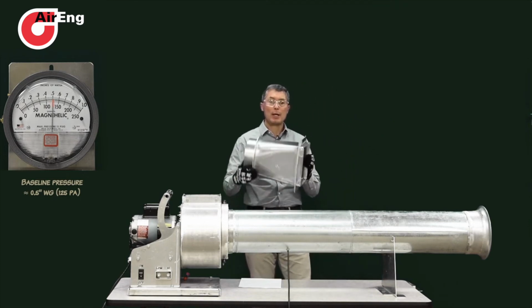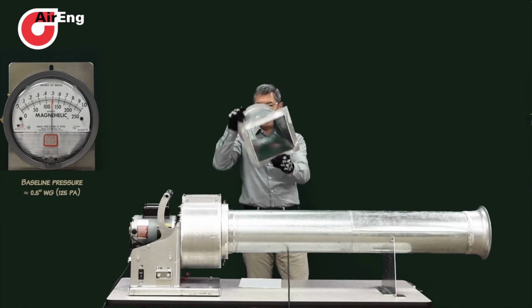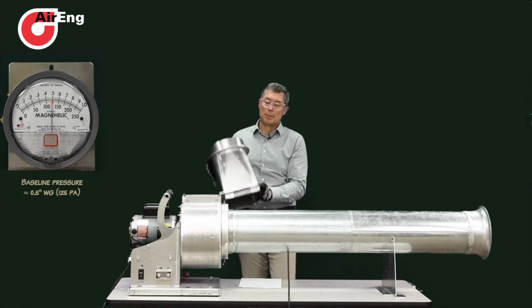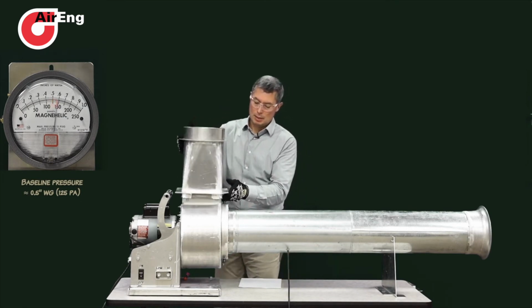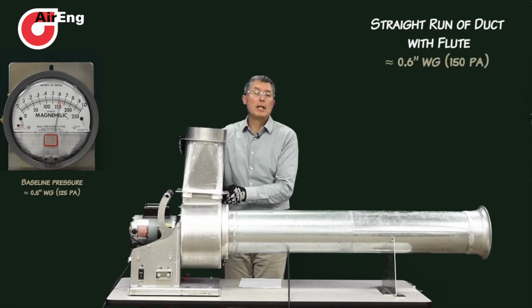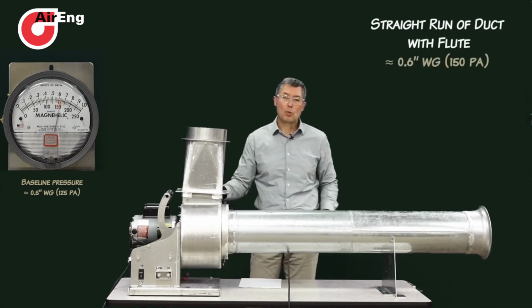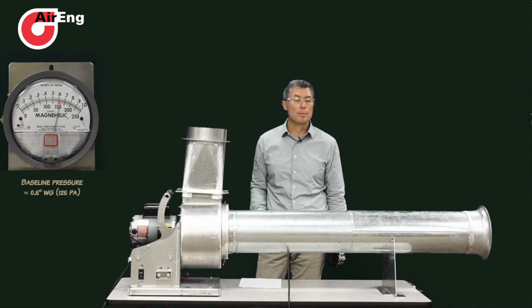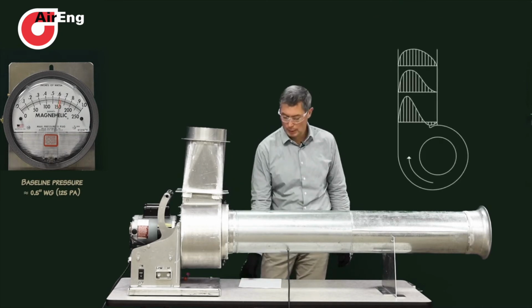And we can show that by utilizing the smaller, shorter, rectangular to round transition. Put it on the fan outlet, and we can see our velocity pressure went up. Not quite as much as it did with the straight run of ductwork, but it still went up pretty sizably.